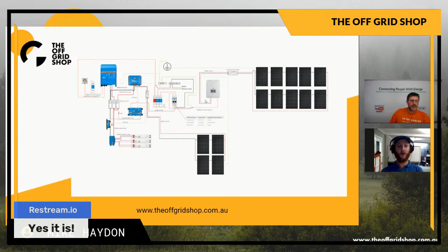Now, if this doesn't happen fast enough, which we've seen in some inverters that are a bit sloppy in how quickly they respond to frequency changes, you can end up with excess energy being produced. When there's excess energy and nowhere for it to go, it goes straight to the batteries. Usually it's not going to immediately damage your batteries, but with lithium batteries the voltage climbs right up, and the BMS has a contactor inside it and switches the battery off. So having something completely programmable and really responsive in a system like this works wonders.